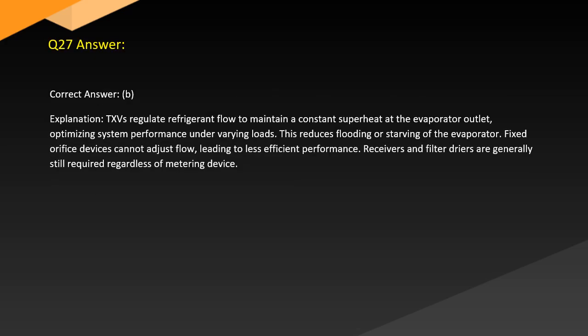Answer. Correct answer: B. Explanation. TXVs regulate refrigerant flow to maintain a constant superheat at the evaporator outlet, optimizing system performance under varying loads. This reduces flooding or starving of the evaporator. Fixed orifice devices cannot adjust flow, leading to less efficient performance. Receivers and filter dryers are generally still required regardless of metering device.